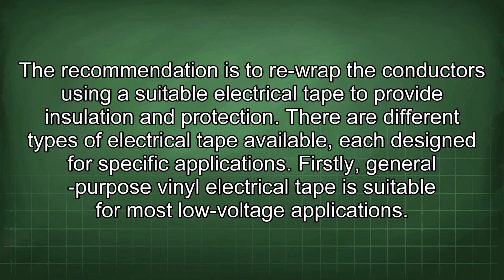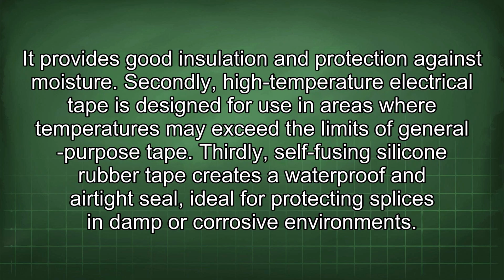There are different types of electrical tape available, each designed for specific applications. Firstly, general-purpose vinyl electrical tape is suitable for most low-voltage applications. It provides good insulation and protection against moisture. Secondly, high-temperature electrical tape is designed for use in areas where temperatures may exceed the limits of general-purpose tape. Thirdly, self-fusing silicone rubber tape creates a waterproof and airtight seal, ideal for protecting splices in damp or corrosive environments.